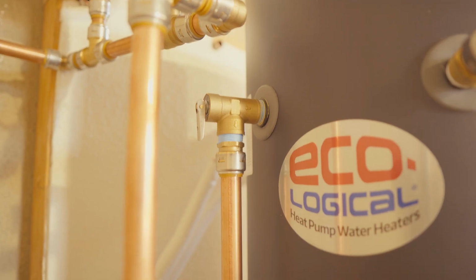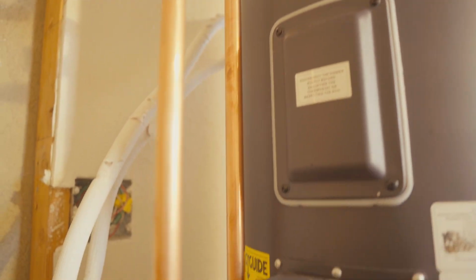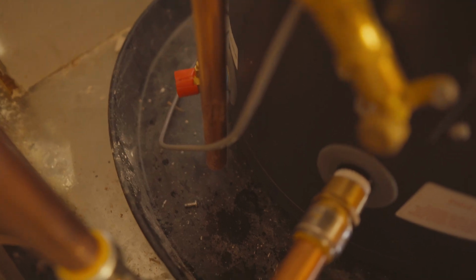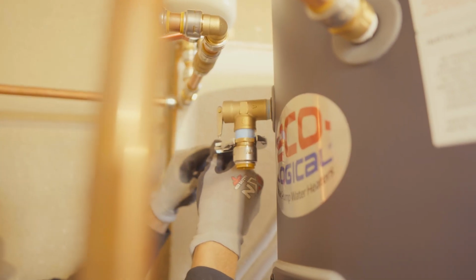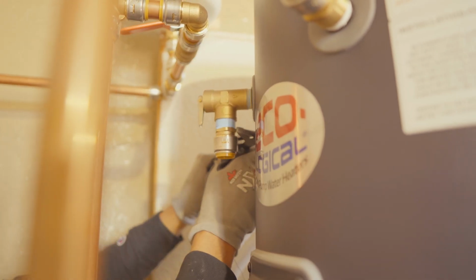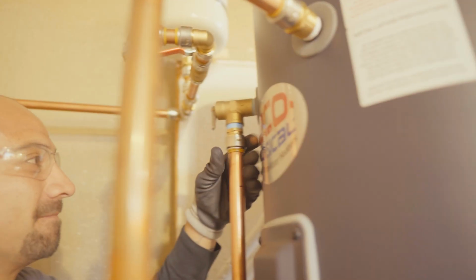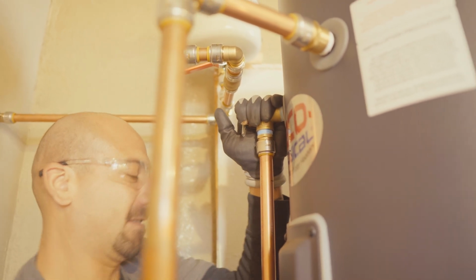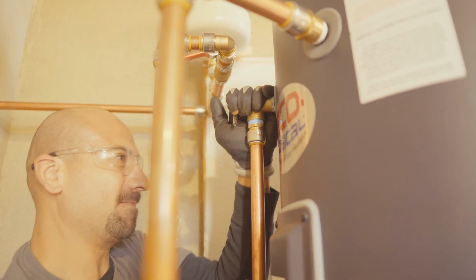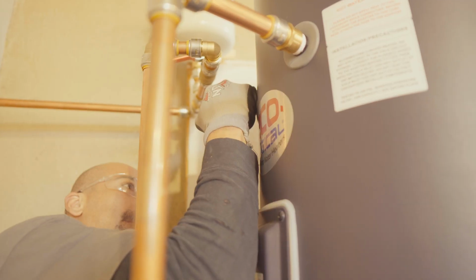Lastly, we install the piping for the temperature and pressure relief valve, also known as the T and P valve. This valve is a critical safety component that releases pressure if the tank ever overheats or becomes overpressurized. The discharge line is run from the T and P valve down to the drain pan so it can safely direct any released water away from the unit.